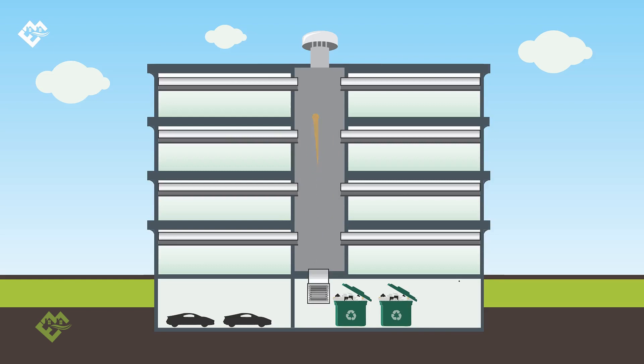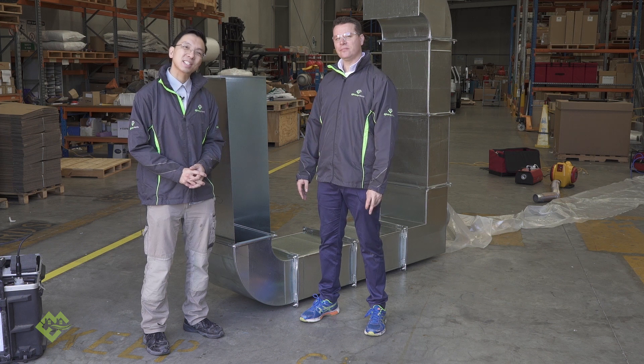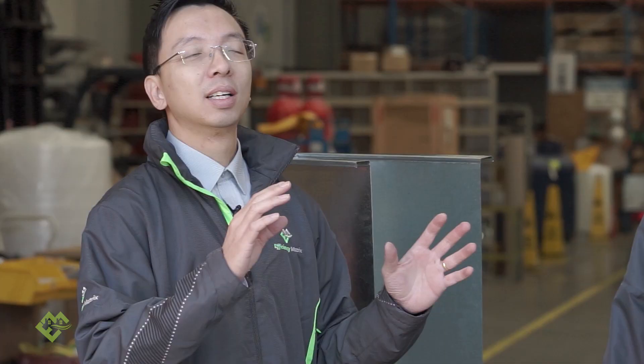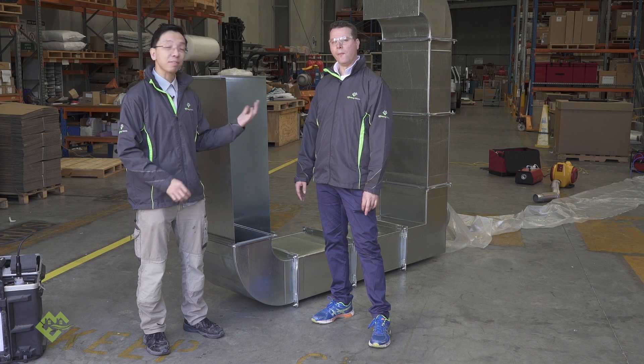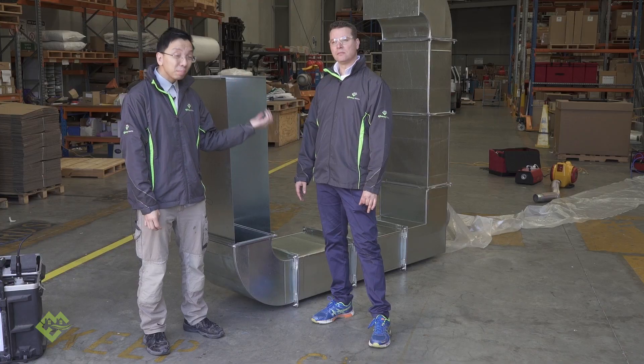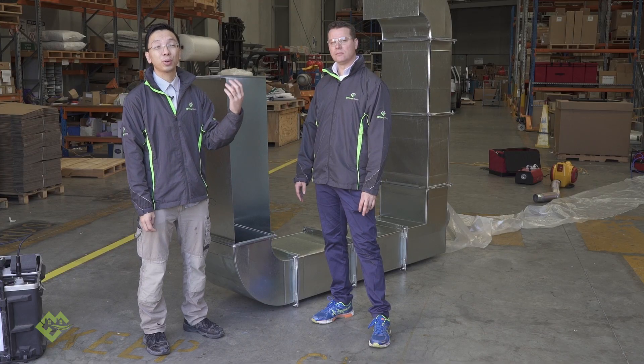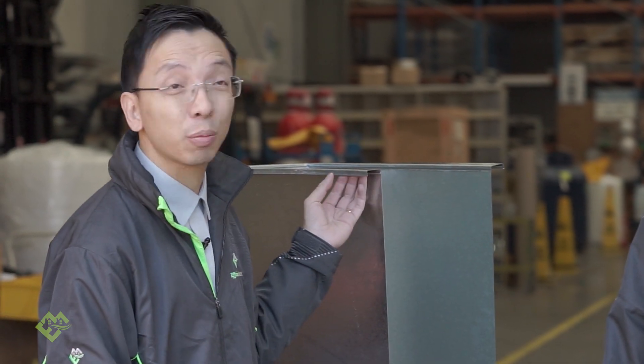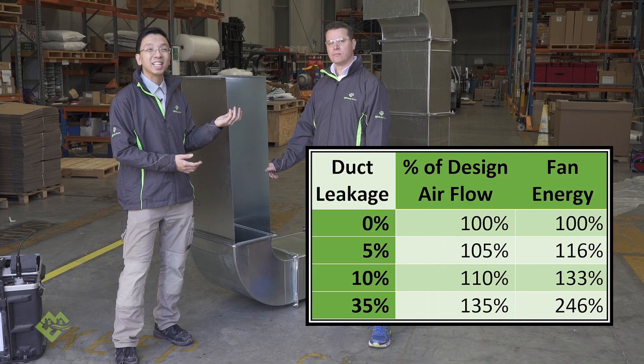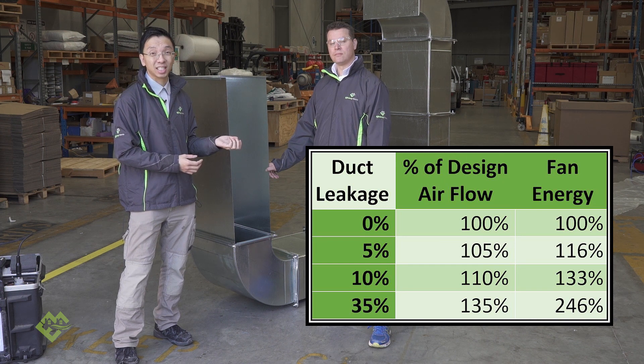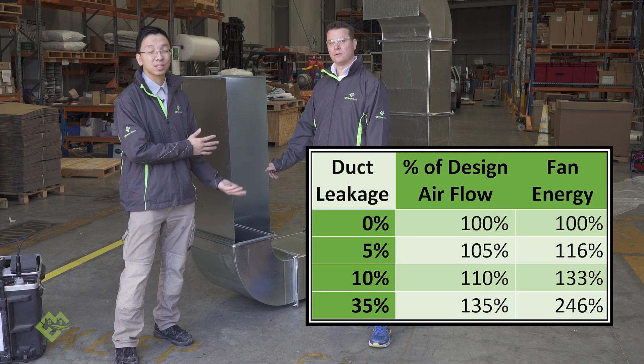Leakage in ductwork is not as straightforward as other wastage because the energy required to generate airflow follows a cube rule. A five percent increase in airflow translates to a 17 percent increase in fan energy. A ten percent increase results in a 37 percent increase. In the worst case, if your ductwork is leaking at 35 percent, you are using an extra 140 percent of energy on top of the original design — a huge implication for fan energy requirements.